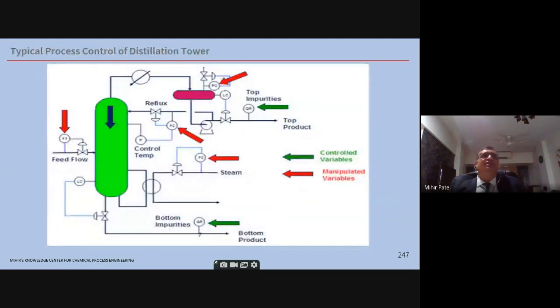Now, typical distillation column controls, what are there? Feed flow control is there. Then you have the reflux inert gases outlet with a pressure control at the top. The reflux drum bottom pump has a reflux flow control valve, which is cascaded to the column temperature, as you can see in the middle. Then the distillate top has a level control. These are typical distillation column controls. Steam at the reboiler at the bottom has flow control. The steam can also be cascaded to column temperature. Then at the bottom, you have a level control for the bottom product. So this is a typical feed process control. Again, a distillation column has more than 10, 12 types of controls.